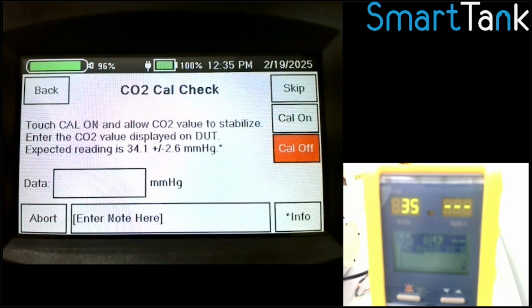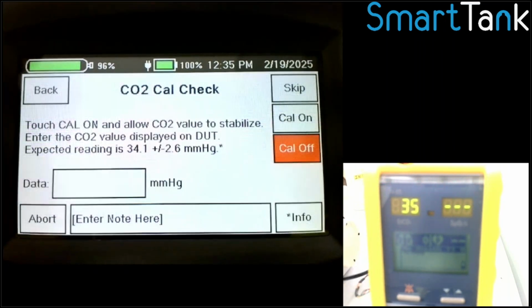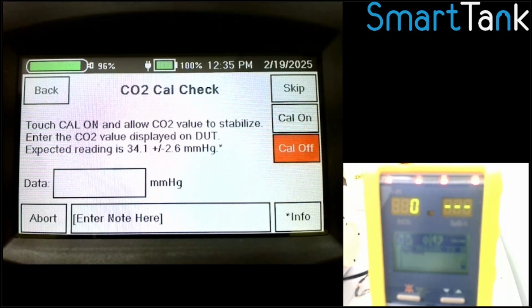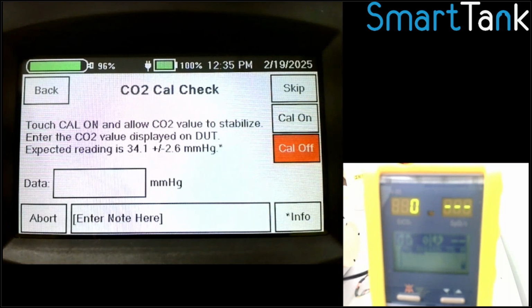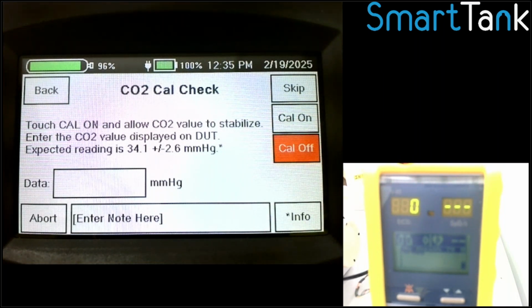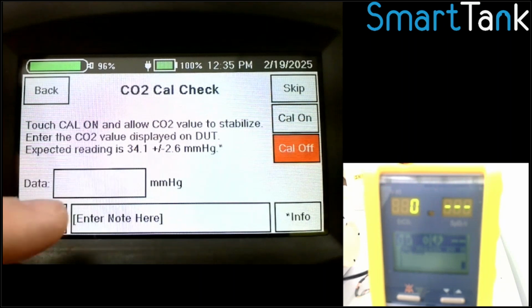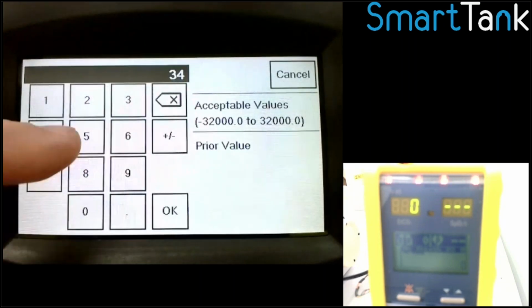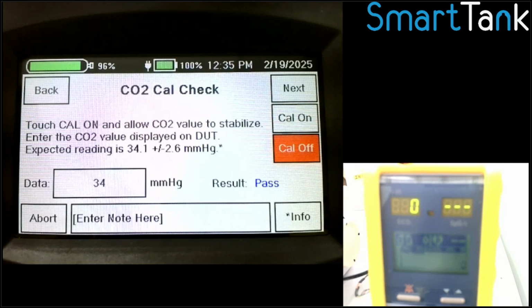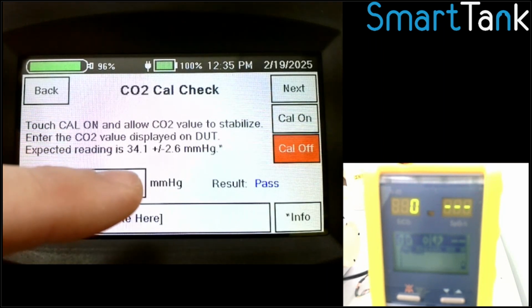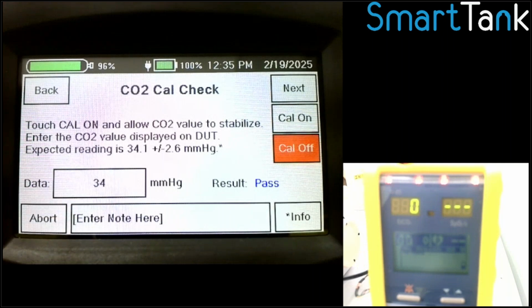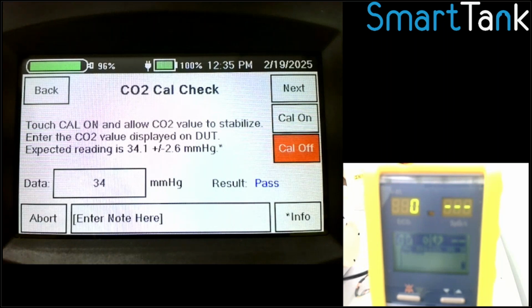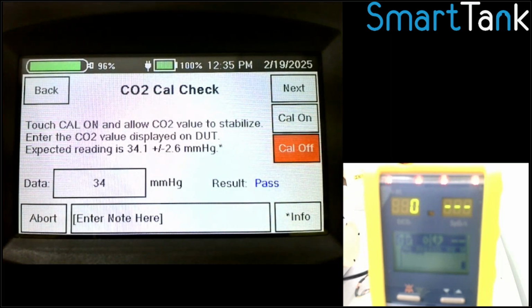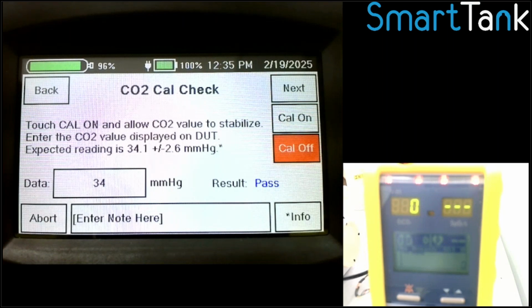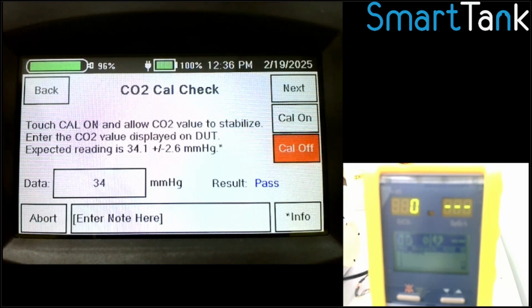There you go. So on this screen now, it's asking us to confirm what the value would be over here. Again, it doesn't show a value because I'm not in the right mode. It has to be breathing to get it in this mode. Anyway, we'll pretend it's this 34, so it passes. If you're paying attention, you'll notice, hey, wait, where did that 34 come from? I'm using 5% CO2. Well, the SmartTank does all the math for you. It uses that absolute pressure sensor, just converts it. I might come back in a week and this will be 32 instead of 34 because the weather's changed or something else. So we're done.